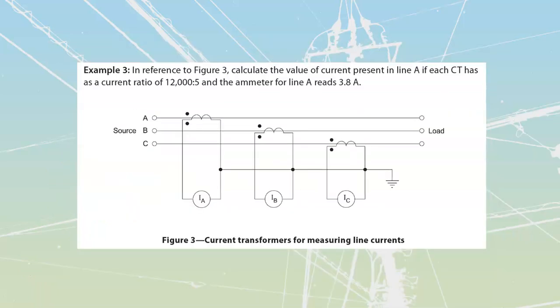Okay, next one that we're going to take a look at is my CTs. Once again, my CTs over here are going to give me a reading off of just what they have pulled through them. I see that the CT connection is once again on the low voltage side connected Y. Once again, let's not worry about that, because if I take a look at the actual CT, the CT itself is just reading that loop, that ammeter.